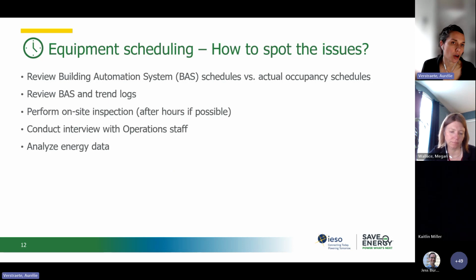This is the first opportunity to address and the easiest saving measure: to stop systems when they are not required. So how to spot that kind of issue? You can review building automation system schedules and compare them to actual occupancy schedules, review BAS graphics and trend logs, perform an on-site inspection if possible, also an inspection during after hours to spot other issues. You can conduct an interview with operations staff and analyze energy data.